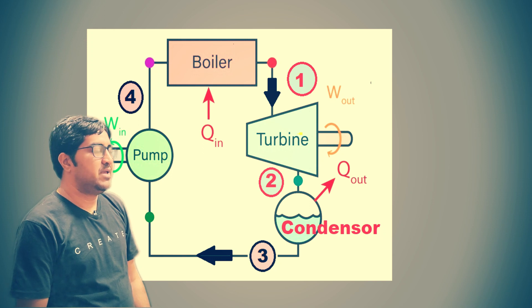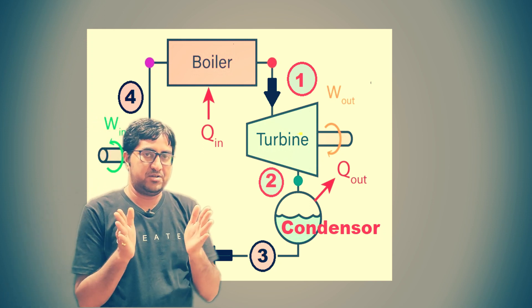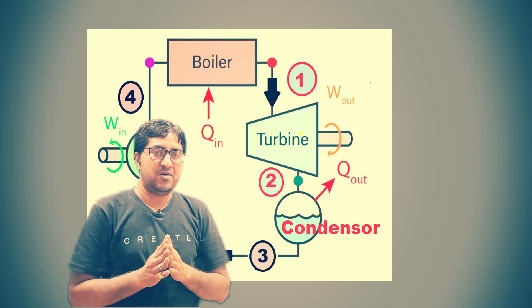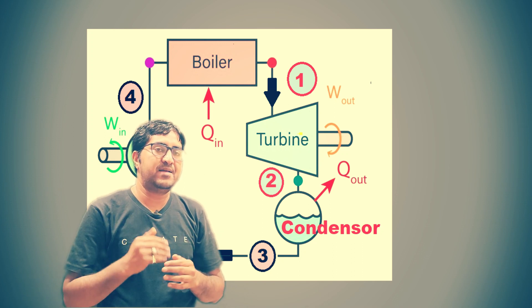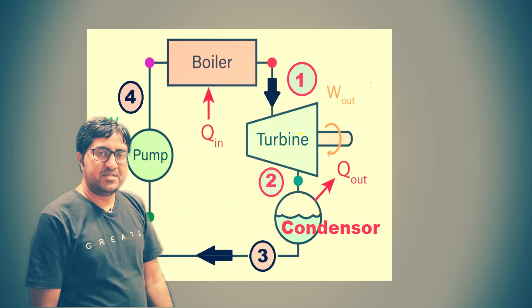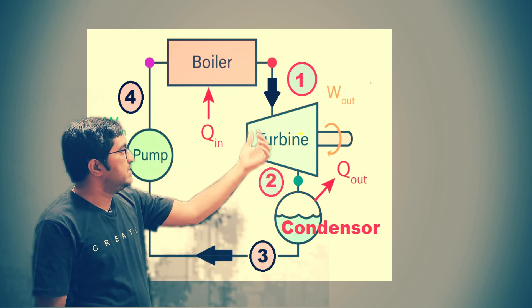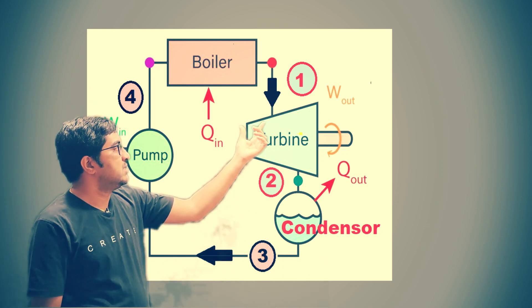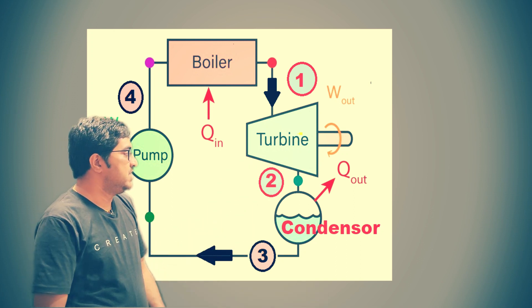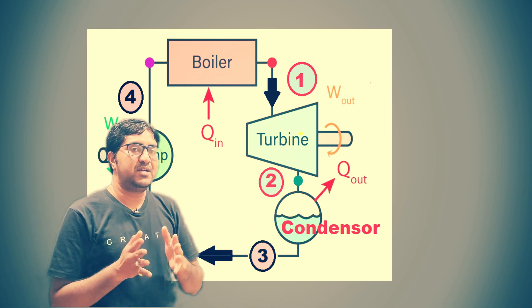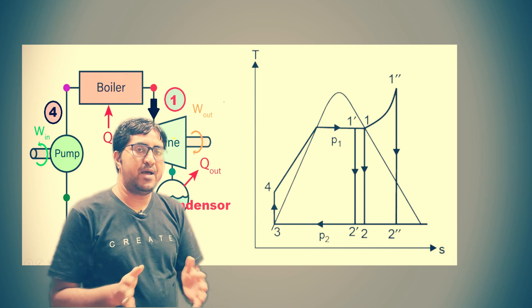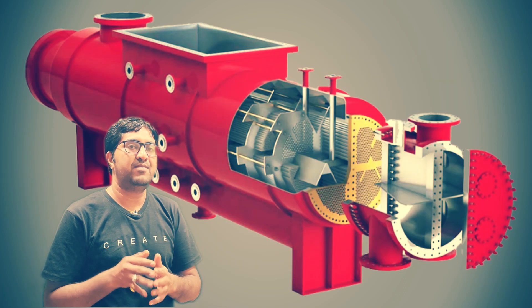Another advantage involves the boiler: when there is a large temperature difference in the boiler, thermal stress is produced — thermal stress is a function of temperature difference. By supplying condensate at a higher temperature, the temperature difference is reduced, so thermal stress in the boiler decreases and the life of the boiler increases. These are the key advantages of the condenser in a thermal power plant.